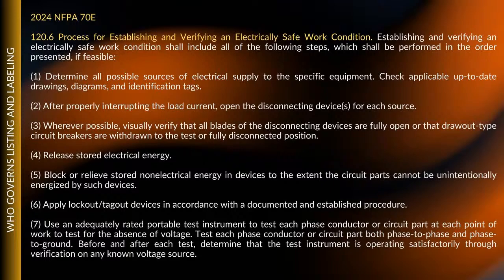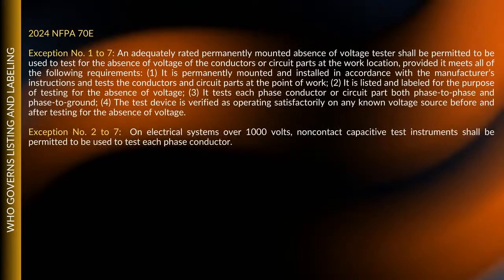Most of the time when they do work permits, that's when you're going to work on it energized. And once you do that, you use a rated portable test instrument in order to test each phase conductor, including phase to phase to ground. They tell you: test the tester, test the circuit, and test the tester again, just to make sure that tester is working properly. We have covered the live dead live test before on here.